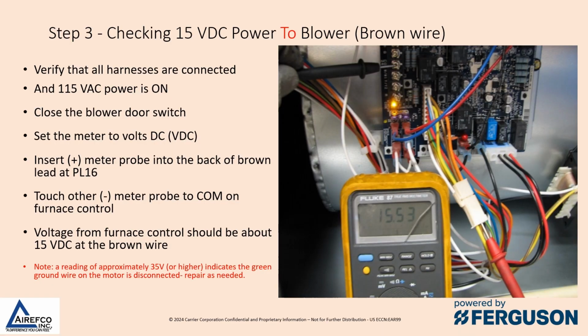So next we want to check the 15 volts DC power to the blower on the brown wire. Verify that all harnesses are connected between the control board and the motor, and the 115 volt power is on. Close the blower door switch. Set the meter to volts DC, VDC. Insert the plus side meter probe into the back of the brown lead at PL16. Touch the negative meter probe to the common on the furnace control board. Voltage from the furnace control should be about 15 volts DC at the brown wire.